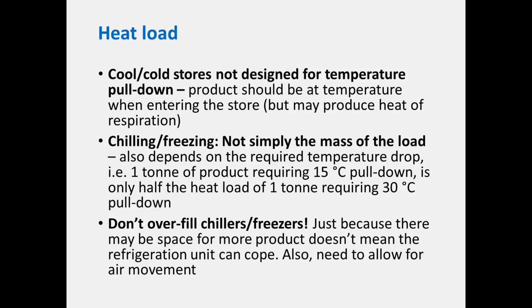When you are dealing with a chilling or freezing problem, the heat load doesn't solely depend on mass. It also depends on how much temperature pull down you have. So, for example, you may have 1 ton of product requiring 15 degrees pull down, and another ton requiring 30 degrees pull down.